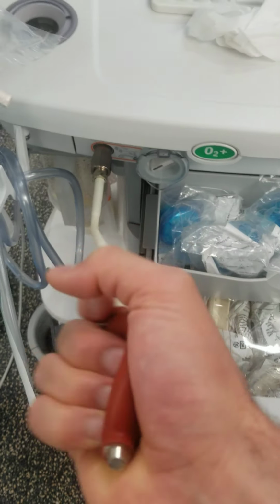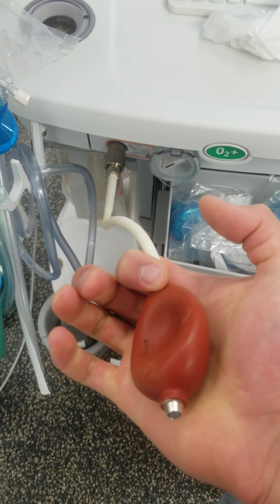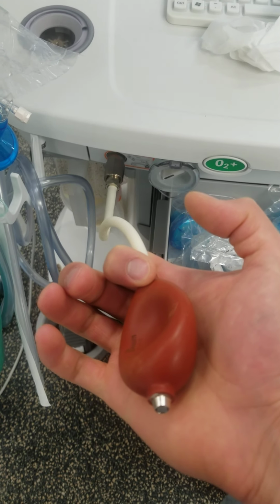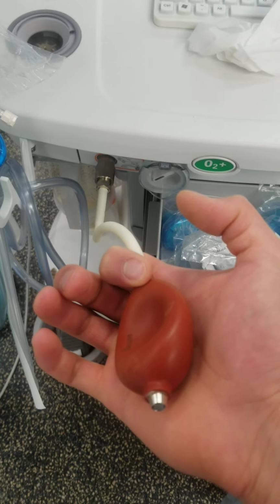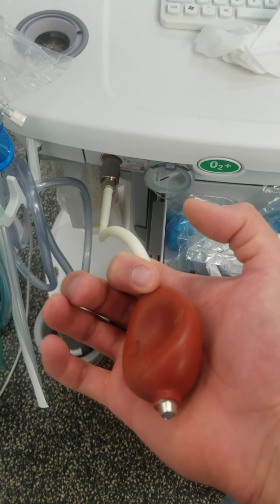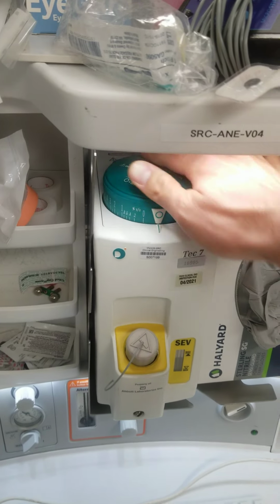So I actually kind of lost suction here. So we'll count 1 Mississippi, 2 Mississippi, 3 Mississippi, 4 Mississippi, 5, 6, 7, 8, 9, 10. All right, we're good. All right, so close your Sevo. Otherwise, you've got gas now going to your system when you start doing a ventilator check.